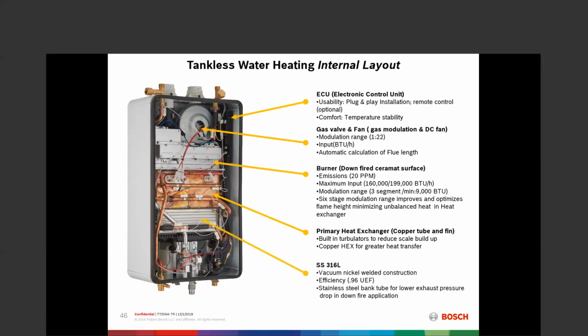Our condensing heat exchanger is stainless steel. Why is it stainless steel? Because it's very corrosive, because we are by design causing condensate in that section there. So it's 316L stainless steel, and it's a series of banked tubes. We'll look a little bit more at those banked tubes in a minute.